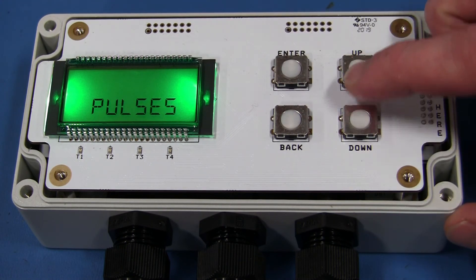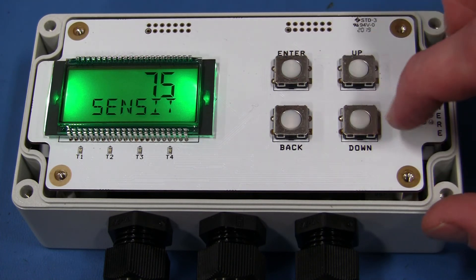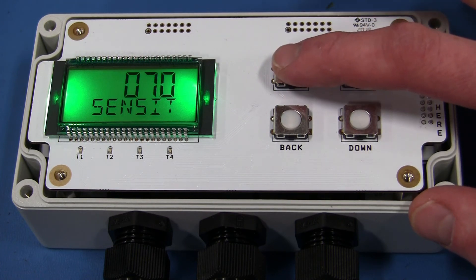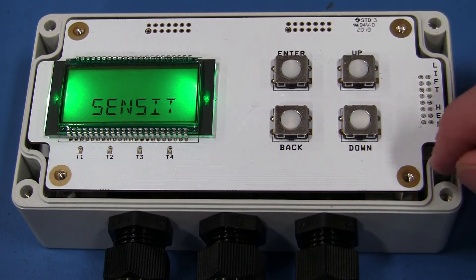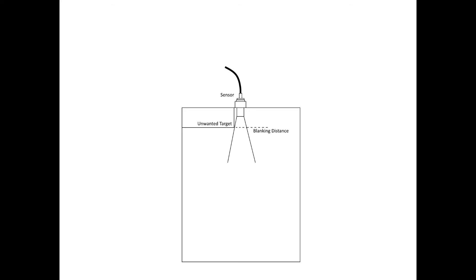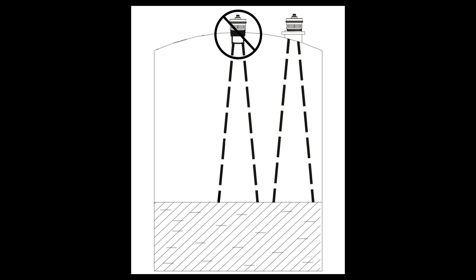Sensitivity and pulse settings can be adjusted for better target acquisition. If your target absorbs sound, these settings can be increased for a stronger ultrasonic pulse. Conversely, if your sensor is mounted in a tank prone to echoing, these settings can be lowered for a more precise reading. There should be a 3- to 4-foot diameter column of unobstructed air between the sensor and target. Ensure the sensor is mounted away from fill spouts, as sloshing may cause false readings. If your tank has a domed top, mount the sensor away from the center of the dome, as this can create echoes that may cause target loss.